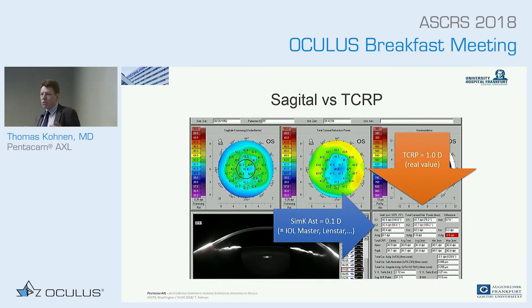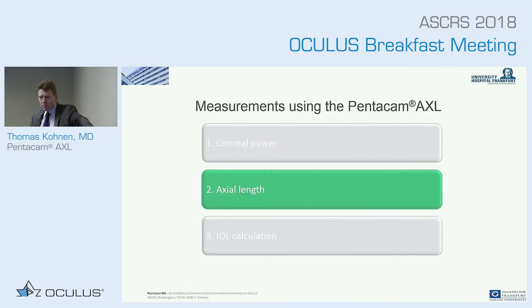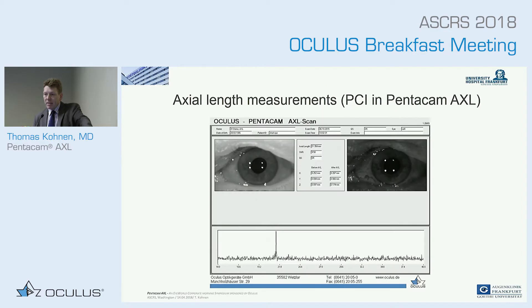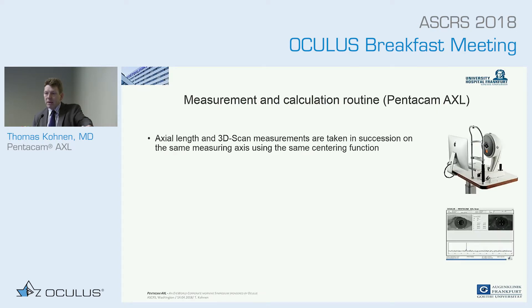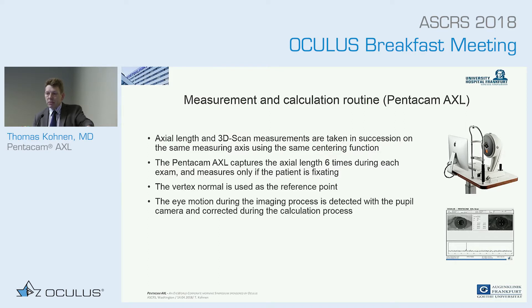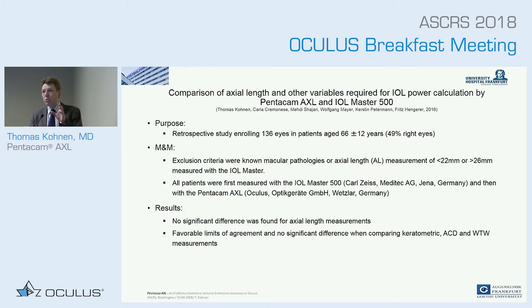On axial length: the gold standard is PCI optical biometry. These developments have occurred over the last 15 years, and Oculus has incorporated this measurement into their Scheimpflug tomographer, putting both machines in one. The Pentacam AXL captures axial length six times during each exam and measures only when the patient is fixating correctly. The vertex normal is used as a reference point, and eye motion during imaging is detected with the pupil camera and corrected during calculation. In our first study, we compared Pentacam to IOL Master 500 and found no difference in axial length measurements.